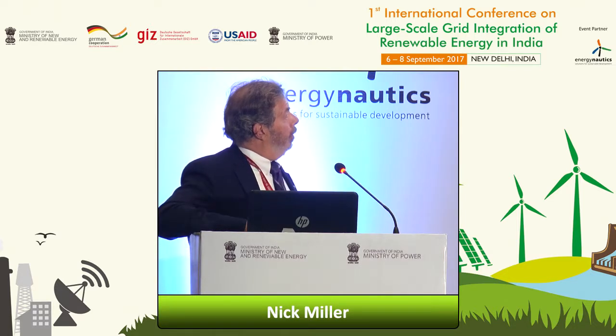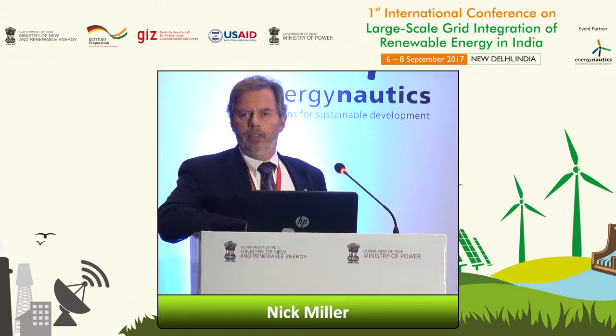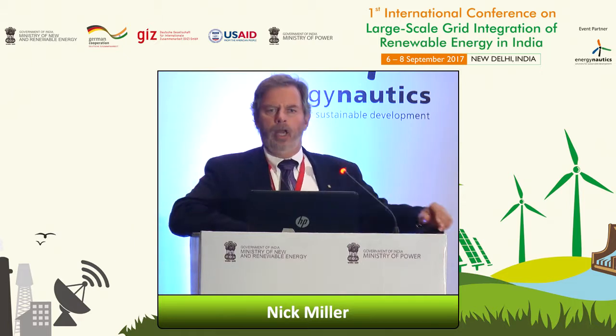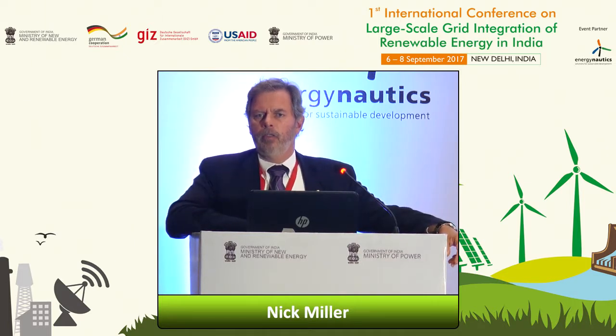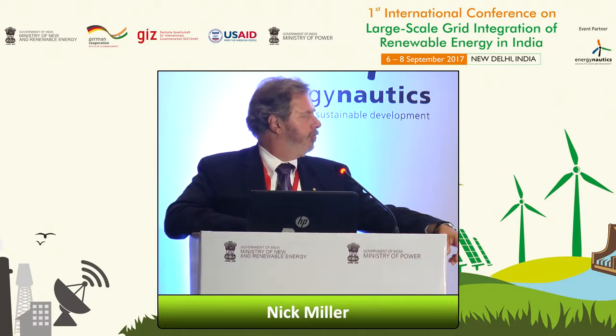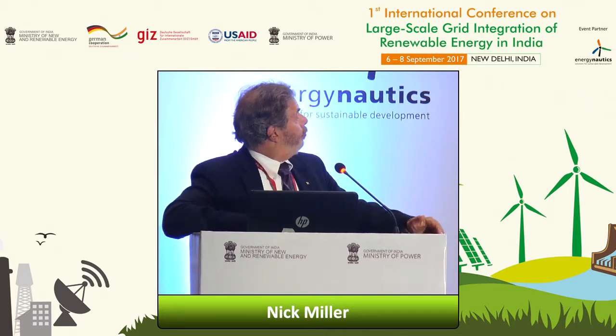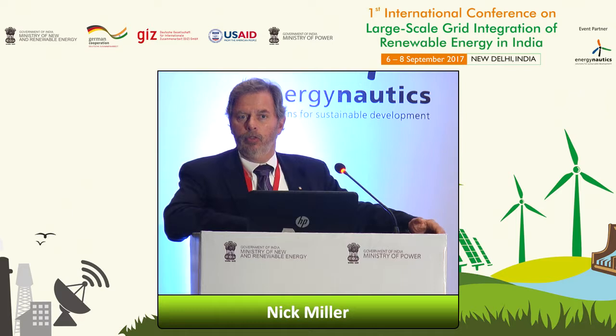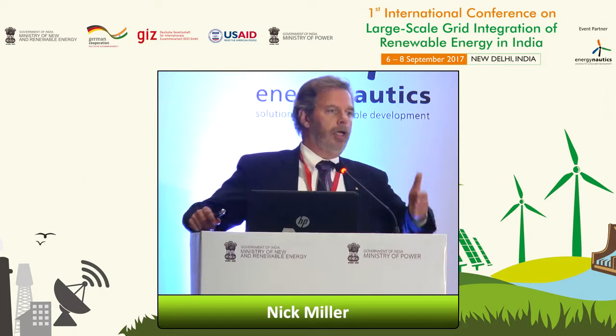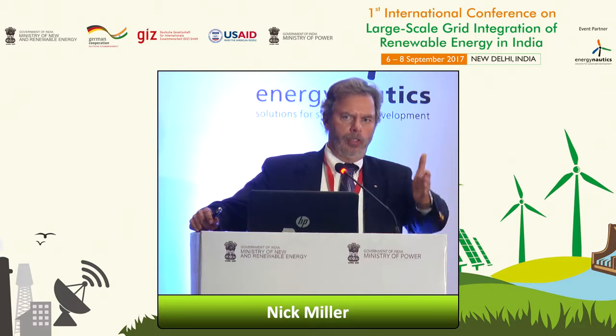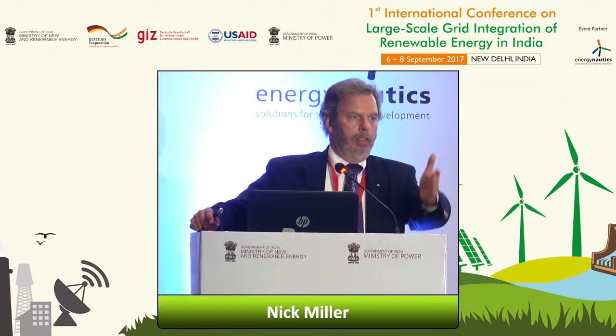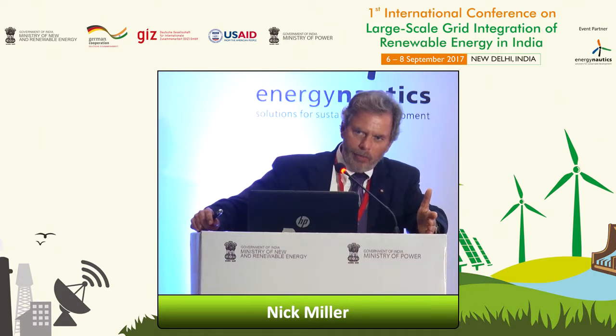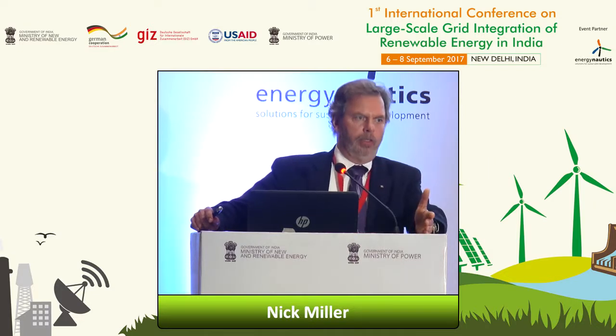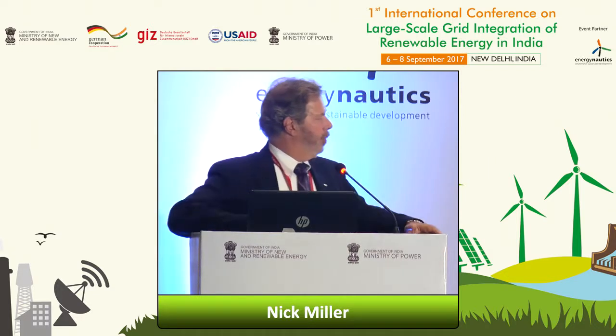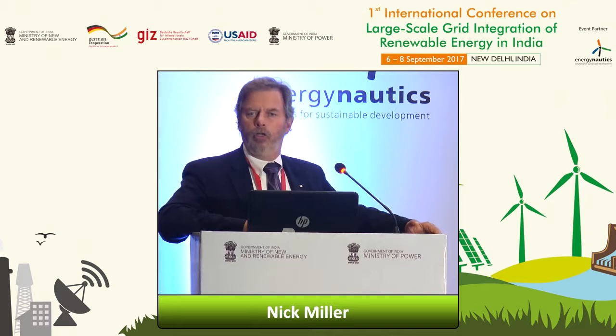So our reliability entity requires that every generator on the power system be tested every 5 years. So there's these 3 MODs, and those are modeling validation requirements. It's a statutory requirement. You've got to go out and test the plant to make sure the generator model is right, to make sure the excitation system model is right, and to make sure the governor model is right.